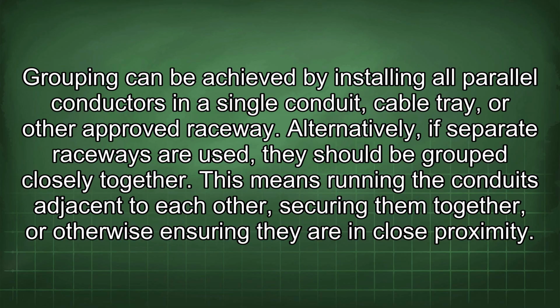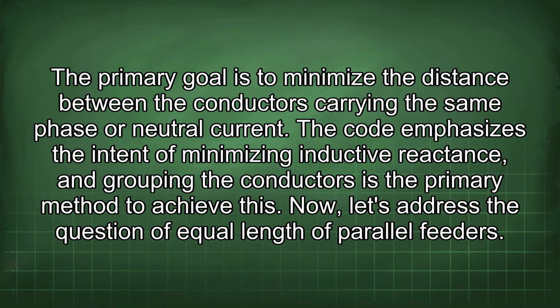This means running the conduits adjacent to each other, securing them together, or otherwise ensuring they are in close proximity. The primary goal is to minimize the distance between the conductors carrying the same phase or neutral current. The code emphasizes the intent of minimizing inductive reactance, and grouping the conductors is the primary method to achieve this.